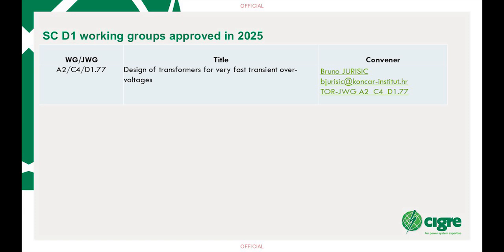This one is about design of transformers for VFTO, very fast transient overvoltages. It's a joint working group looking into how to design a transformer suitable for use in GIS, where a lot of faster transient overvoltages happen compared to more traditional transformers. There are standards for transformer testing using slower voltages, but because of this VFTO, more testing techniques have to be developed. This is covered in this work committee.